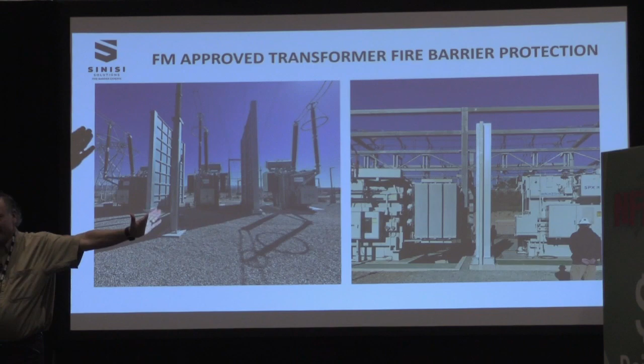But this transformer failing is going to blow shrapnel, fire, flaming liquids, and take out the other two transformers. That's what you do not want to happen. You want to have separation and containment to assure that one transformer failing doesn't affect the other two.